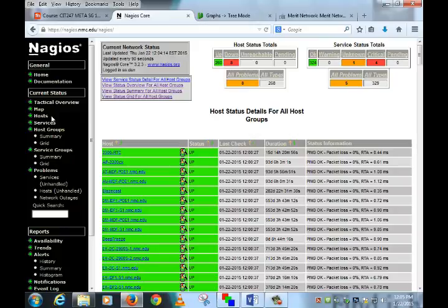Just out of curiosity, how do we determine the backup battery life? In the server room, yeah. I'm just thinking 14 minutes in, I know it's a generator, it's absolutely not enough. Our backup system is the generator. It is not the battery backup at all. The battery backup in there is for power conditioning, and for the 60 to 90 seconds it needs to spin the generator up if there's a power failure.